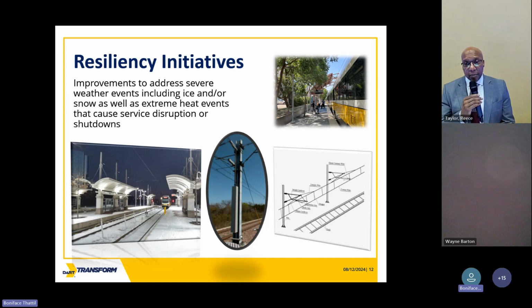During the summertime, the wire stretches and becomes sagging over time. With this counterweight system, the term is bottom out, right? When it bottoms out, there's no more adjustment required or available for maintaining that tension. So what we've explored is changing this design out to an auto tensioning system. It's like a spring tensioning system that will eliminate this counterweight system, and we're looking forward to incorporating that over time as an example.